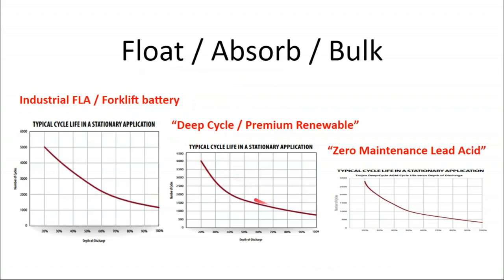The float charge is about being careful, once you get up to the top of the battery voltage, not to apply over voltage. Then there's an additional maintenance charge that raises the battery state of charge and voltage way up to the very top. As soon as you take the charge current away, the battery voltage drops back down. You only do that with unsealed batteries.